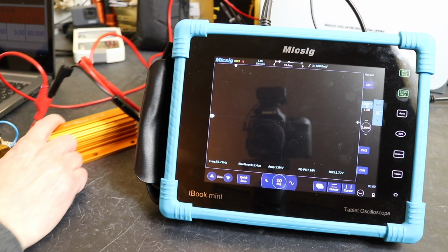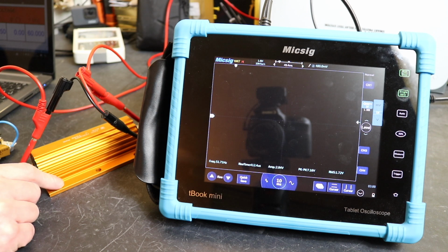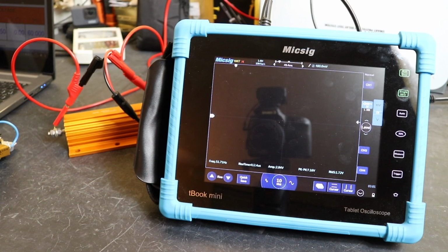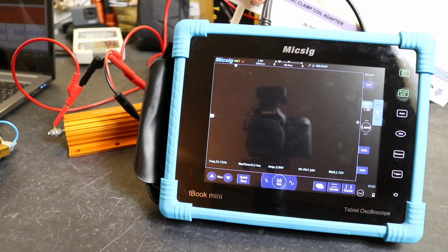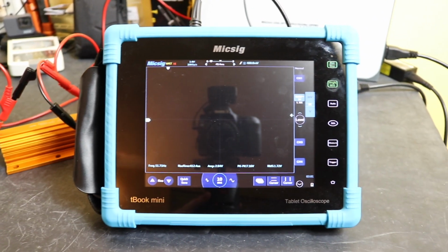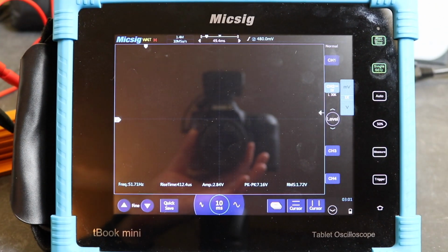So push that one to one side, and we've now got this slightly enlarged resistor, but this is 0.1 ohm resistance value. So now my burden has significantly decreased on the test set. I can now get another set of readings. So we'll just demo the 20 amp AC. We're on to the 50 turn coil at the back here that you perhaps can't see. Slightly out of picture, we'll zoom into the scope so you can have a look.